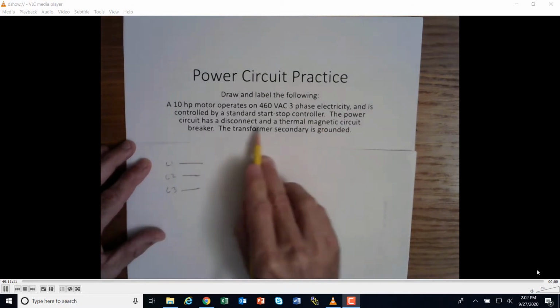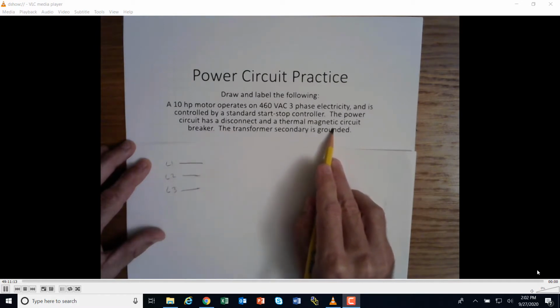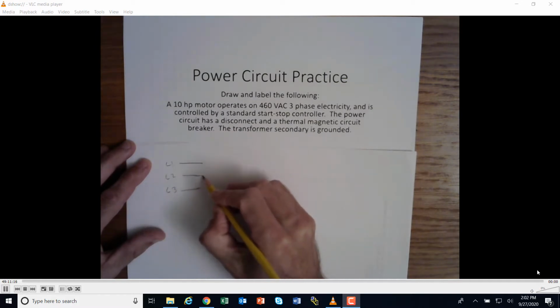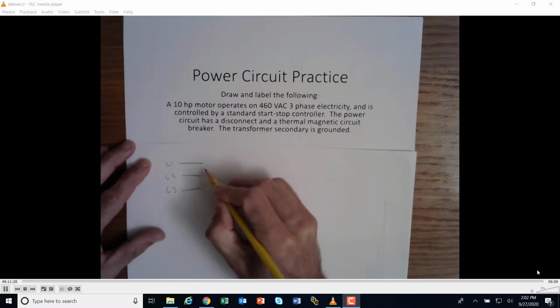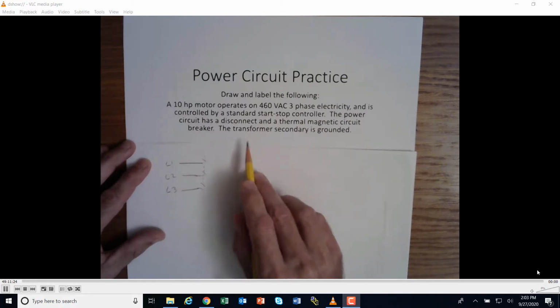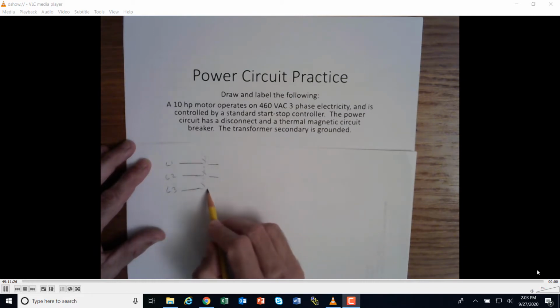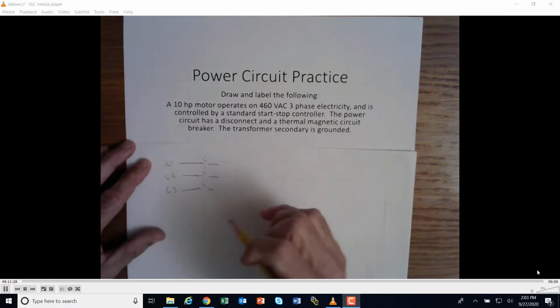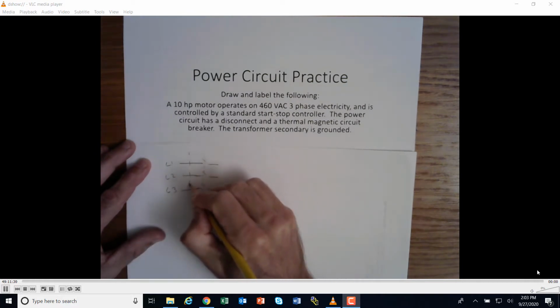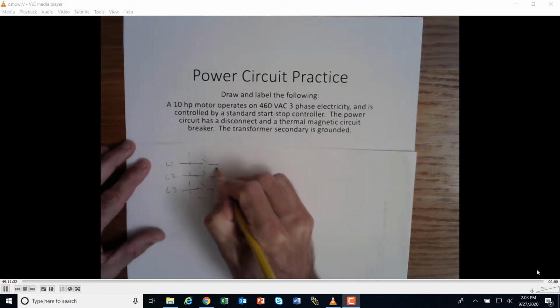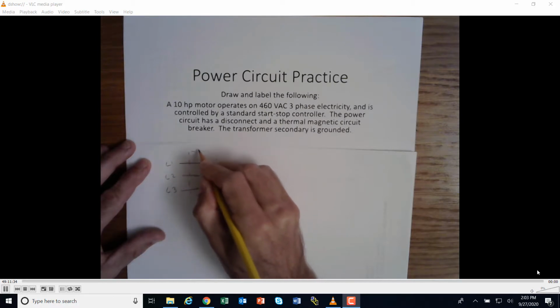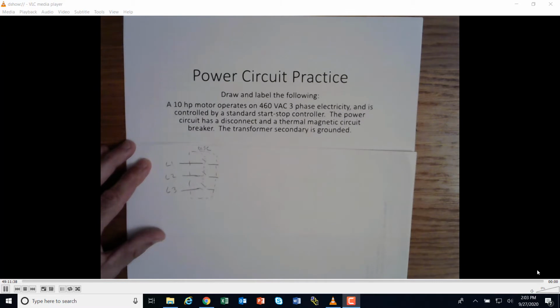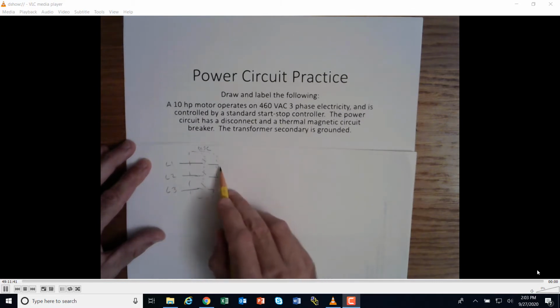Let's take a look. The power has a disconnect and a thermomagnetic breaker. So what we're going to have right here is a disconnect right there. Okay. And this is probably like a knife blade disconnect where you just pull the handle and it shuts. So I'm going to draw a line around this, and I'm going to label it as DISC. That's my disconnect. So I can flat out kill the power there just from that disconnect.